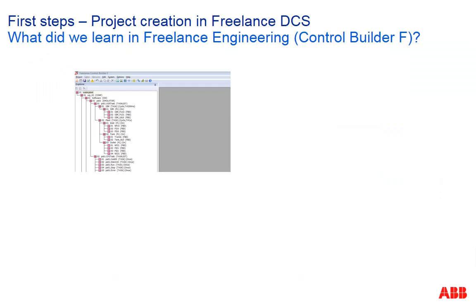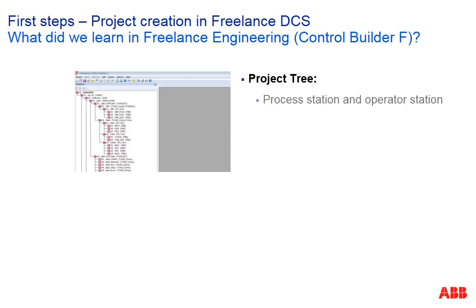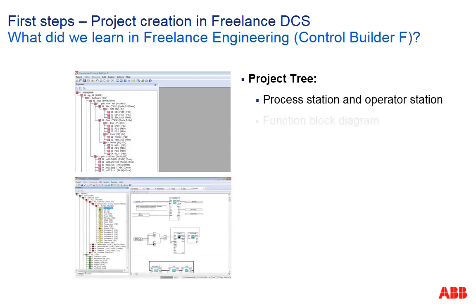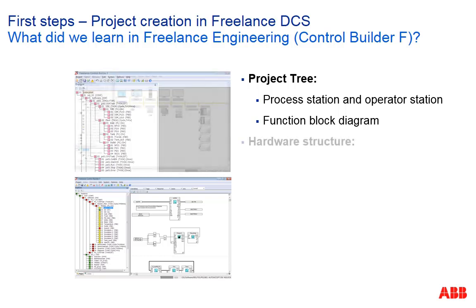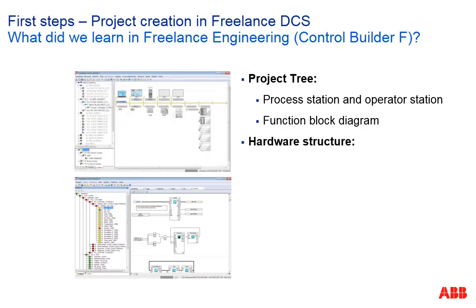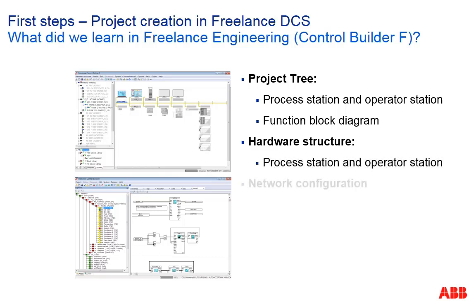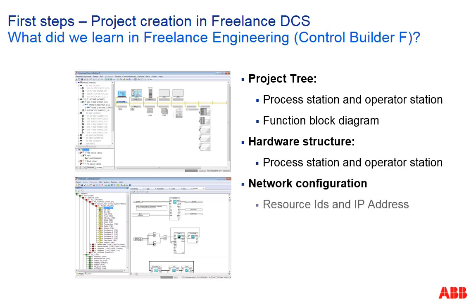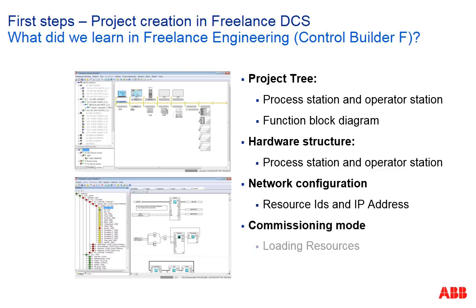To summarize what we have learned in this session. In Control Builder F we created a new project, inserted a process station, an operator station and a function block diagram in configuration mode. Then we inserted a process station and an operator station in the hardware structure and assigned them to those defined in the function block diagram. We specified the resource ID and IP addresses for both stations in the network configuration. We started DigiVis and the controller emulator. We loaded both the process station and the operator station. And then in DigiVis we opened the faceplate of the tag.